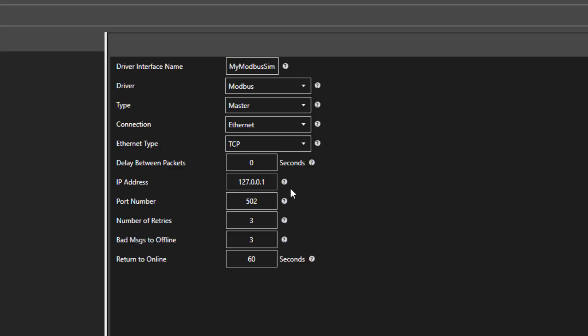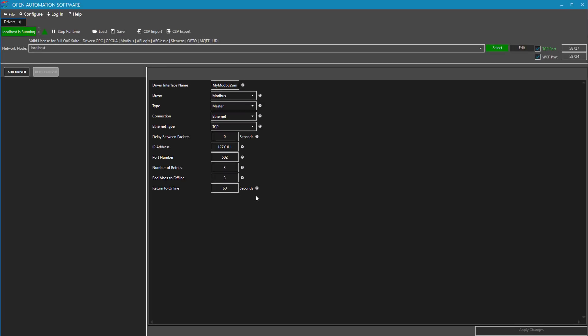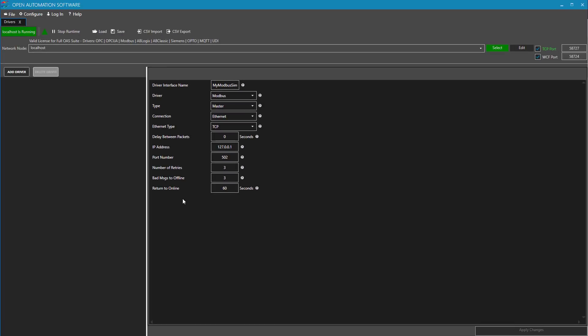The last parameter on this screen is Return to Online. If the device goes offline and we are not able to connect to it, this is the frequency at which the OAS service will try to reconnect. The default is 60 seconds, but that can be adjusted to be faster or slower. Now that we have all of the information filled out, we select Add Driver.